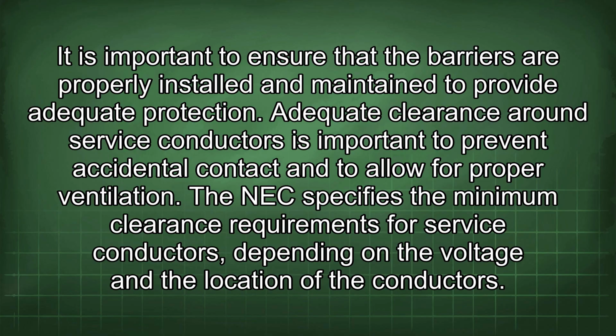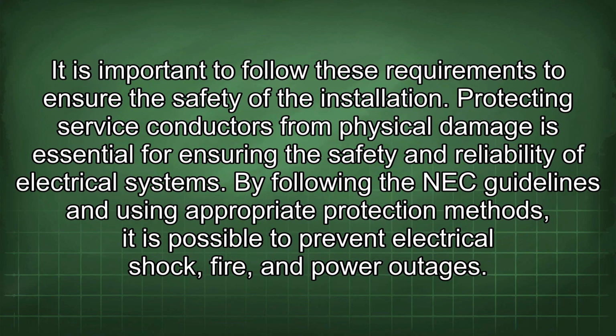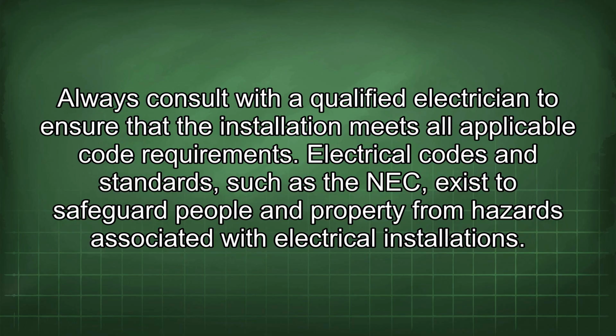Adequate clearance around service conductors is important to prevent accidental contact and to allow for proper ventilation. The NEC specifies the minimum clearance requirements for service conductors depending on the voltage and the location of the conductors. It is important to follow these requirements to ensure the safety of the installation. Protecting service conductors from physical damage is essential for ensuring the safety and reliability of electrical systems. By following the NEC guidelines and using appropriate protection methods, it is possible to prevent electrical shock, fire, and power outages. Always consult with a qualified electrician to ensure that the installation meets all applicable code requirements.